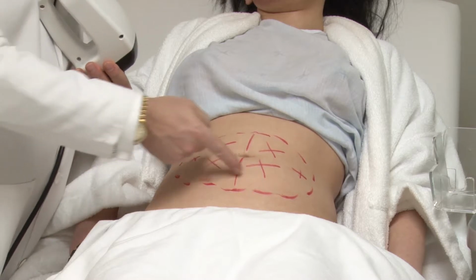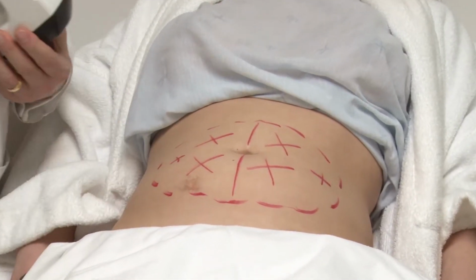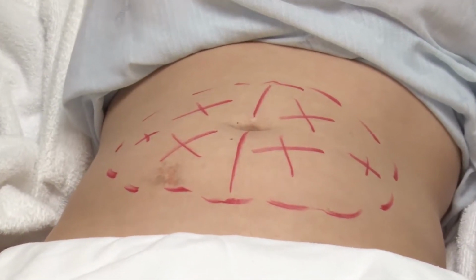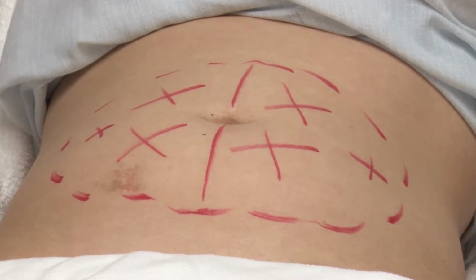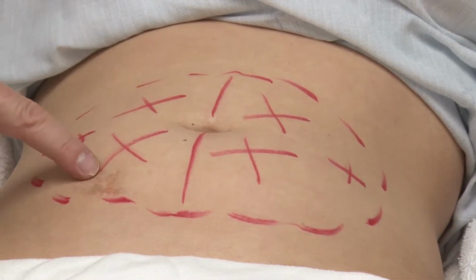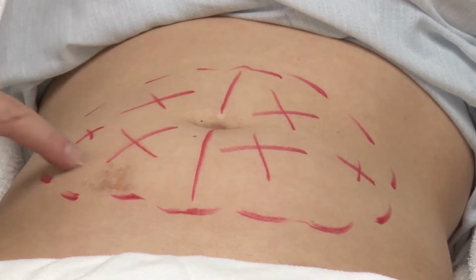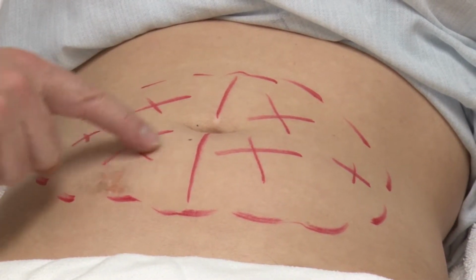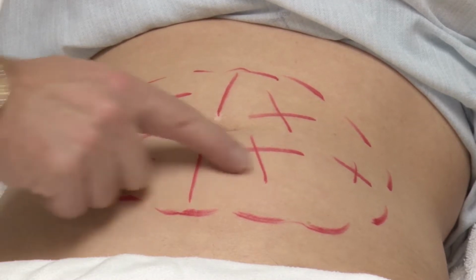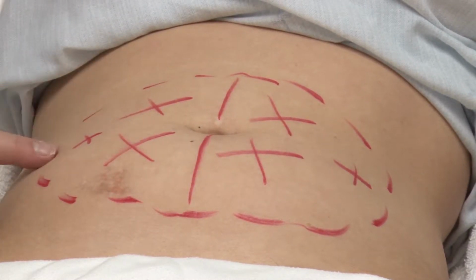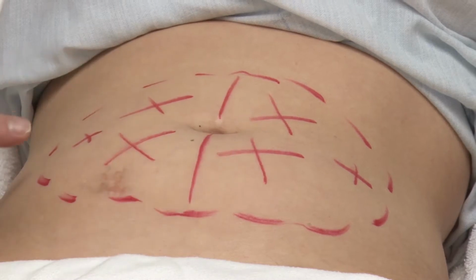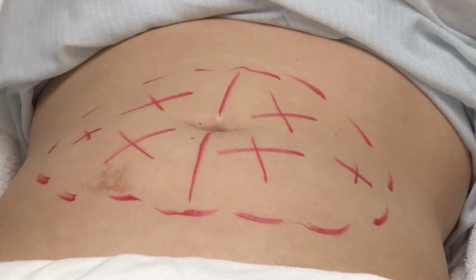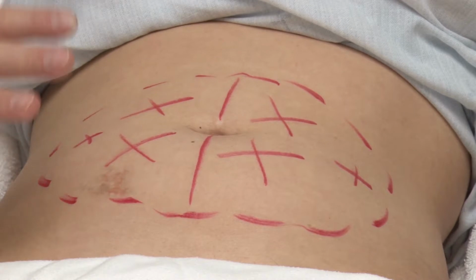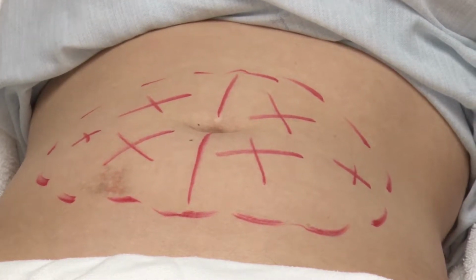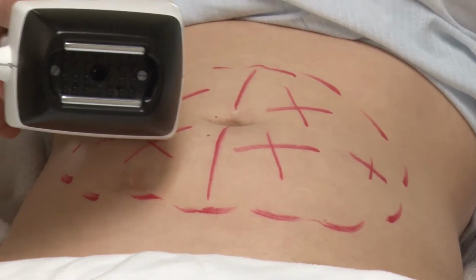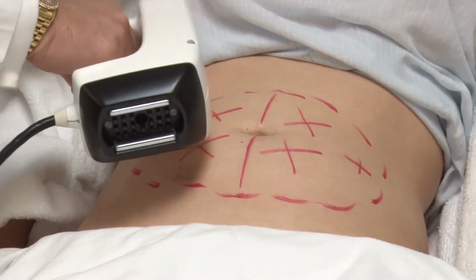So if we look at our zone, zoom in here, we've got our periumbilical pot. Remember our strategy. We're going to heat to the endpoint, 42, 43, 44 degrees, and then start firing high voltage pulses. We want to treat for 10 minutes on an area, but we'll divide that into 5 minutes, 5 minutes, 5 minutes, 5 minutes. If this was the outer thighs, you do one outer thigh for 5 minutes, the other one for 5 minutes, first one for 5 minutes, second one for 5 minutes. Total on time for the whole area is 20 minutes.